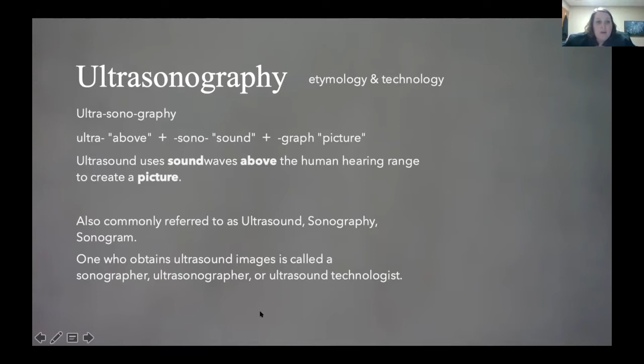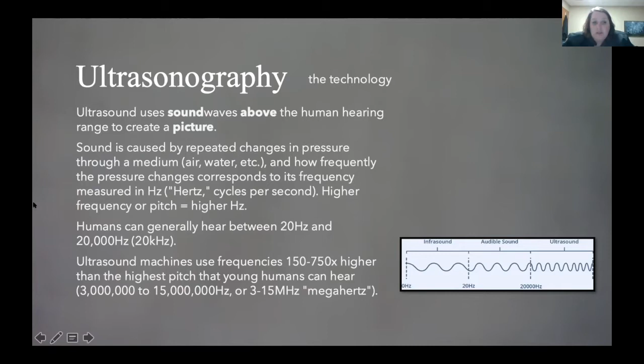So, the technology behind it. Like I said, ultrasound uses sound waves above the human hearing range to create a picture. Sound is created by repeated changes in pressure through a medium, usually air, water, etc., and how frequently the pressure changes corresponds to its frequency, measured in hertz, or Hz, cycles per second. The higher the frequency or pitch, the higher the hertz. Humans can generally hear between 20 and 20,000 hertz. Ultrasound machines use frequencies 150 to 750 times higher than the pitch that young humans can hear. So it uses a much higher level.